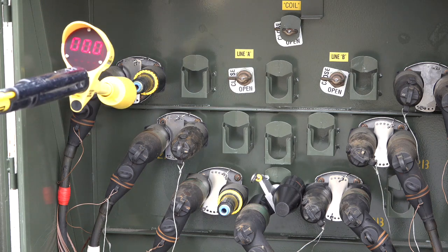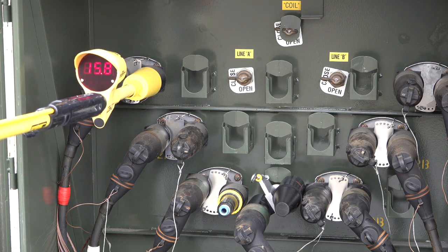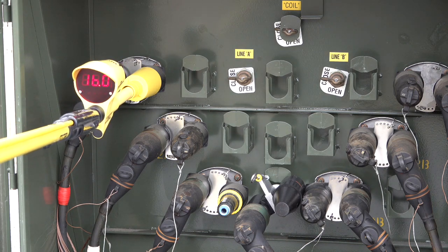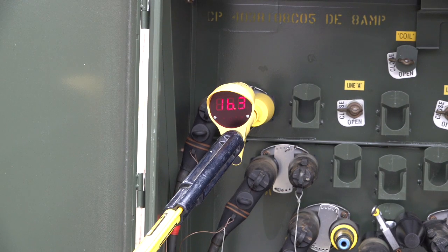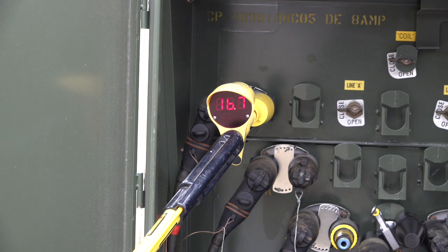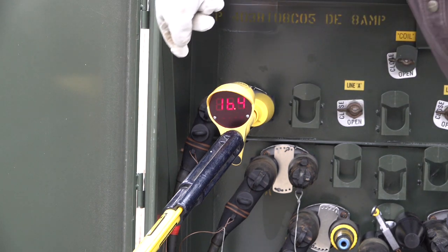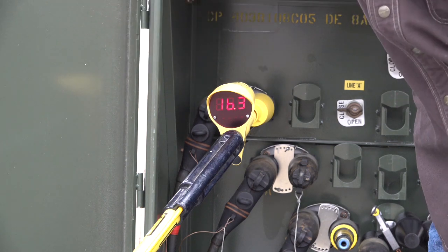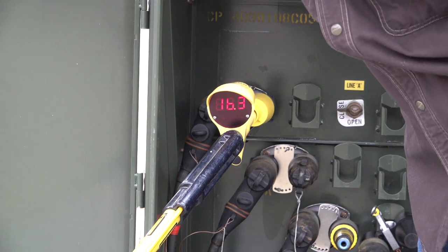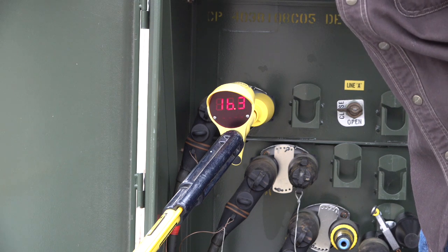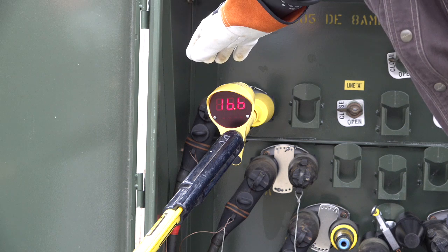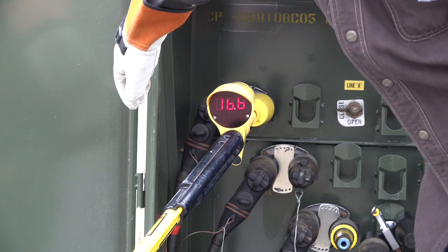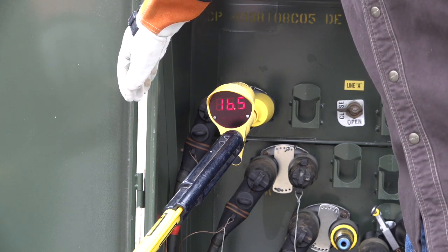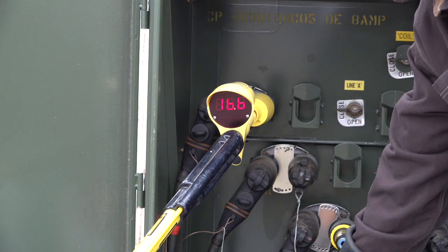Now let's notice what happens when we insert the VD1000 into the bushing adapter closest to a ground plane. The voltage is roughly 500 volts higher. The reason why the voltage display is higher is because the VD1000 is now closer to a ground plane. Notice the distance to the top of the cabinet. Notice the distance to the right of the meter is approximately the same as the lower bushing adapter, but to the left is much closer. The large ground plane above and to the left of the meter will adversely affect the reading versus the lower bushing adapter. Notice how close proximity to my glove also adversely affects the reading. I'm a ground plane to the meter, so this will cause the reading to go higher. The distance below the meter is fine.